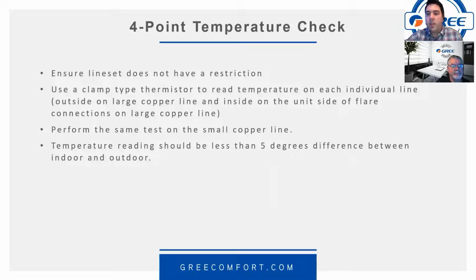So what we're saying there is that you're taking the temperature of one copper line, not the line set. You're taking the temperature outside as close to the service valve as you can get, and inside as close to the manifold of the indoor coil as you can get. Sometimes that would mean removing the outer shell of the indoor unit so you can see the coil and everything, if you can't get to the back of the unit where the line sets come out, but as close to that manifold where it enters the indoor coil.